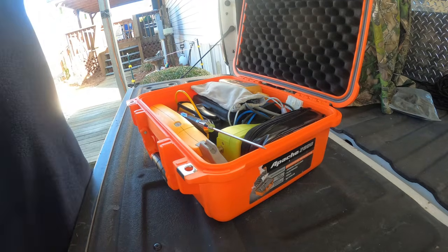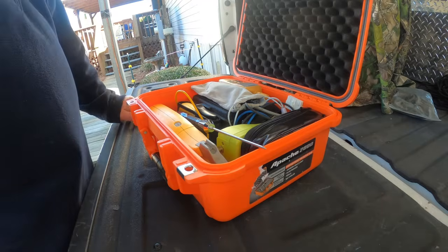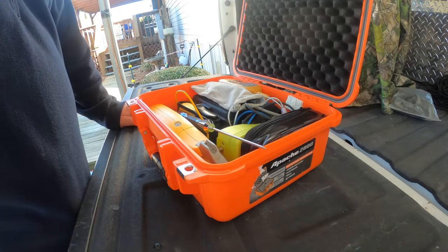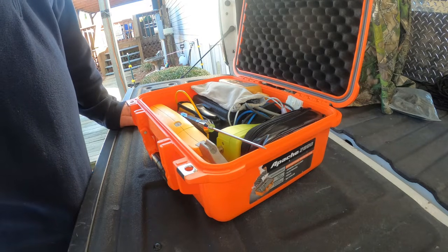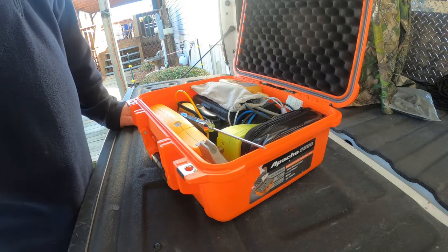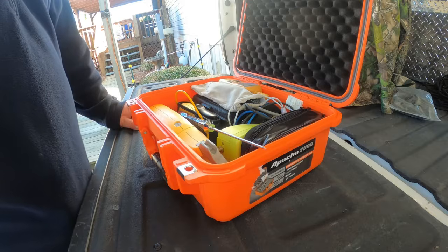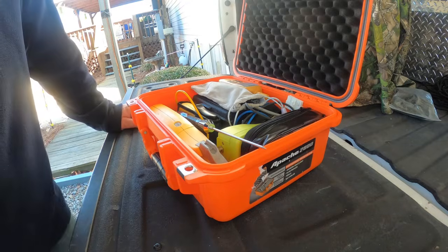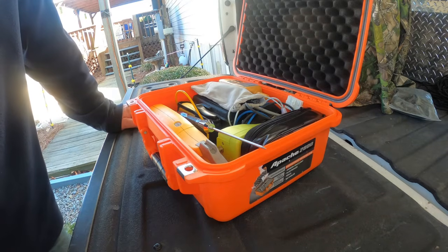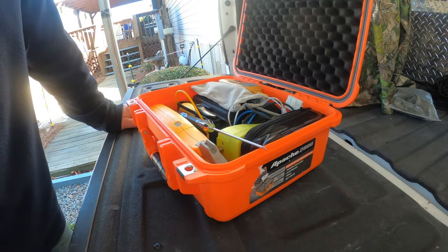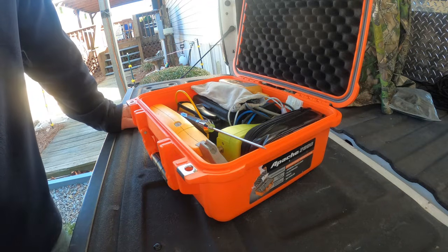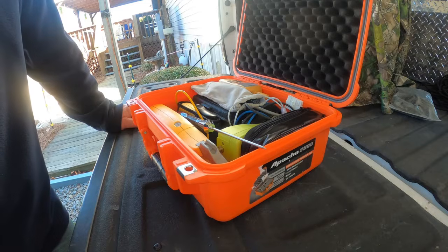Ohming out the windings on those, checking those typically. Sometimes your wiring diagram, you can't read it. Maybe it's some kind of aftermarket motor that's been put in it. Somewhere along the line, you're trying to figure out which speed is which speed. So when you're checking your speeds on a PSC motor, typically you're going to ohm out between your neutral or your common, whether it's a 115 or 230 volt motor, and you're going to ohm that against each one of your speed wires.